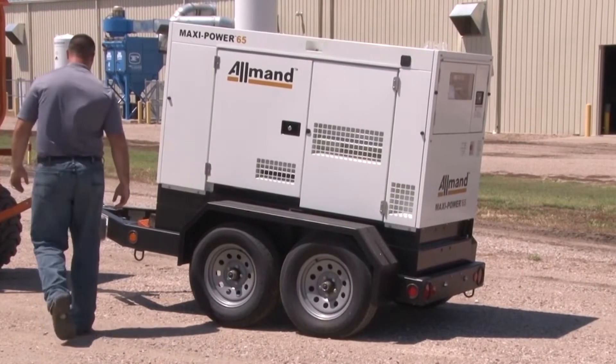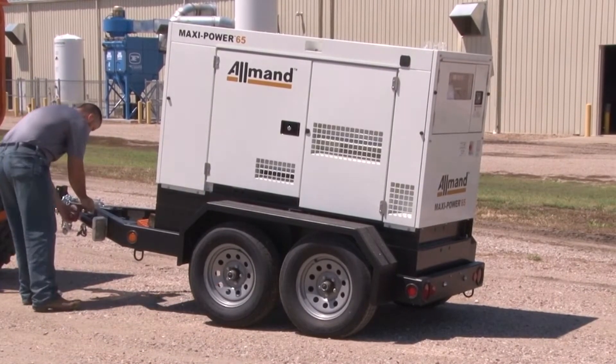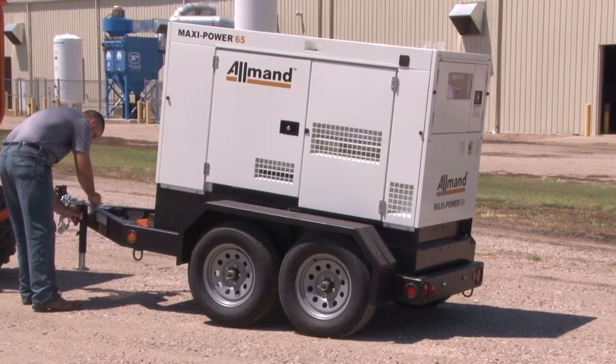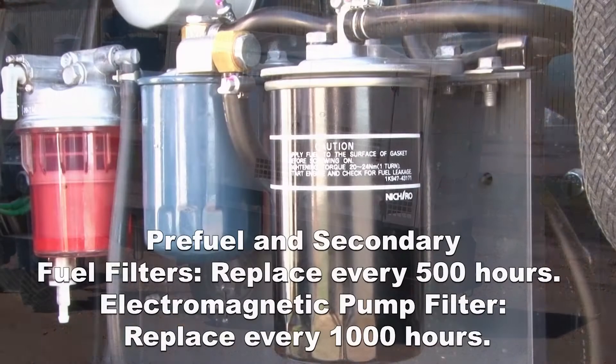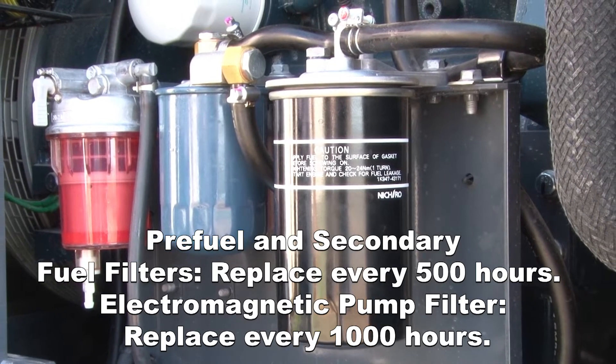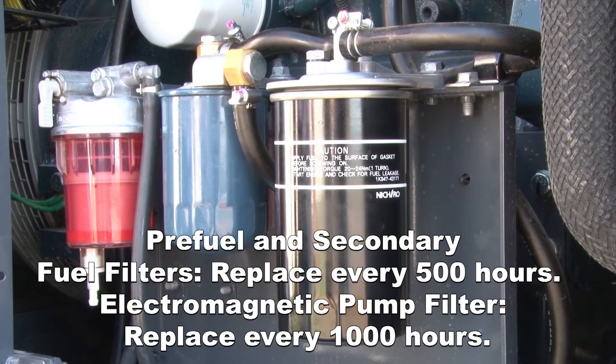Accessible and reliable power is essential to the work that you do. With proper maintenance, Allmand Maxi-Power mobile generators will be ready for you when you need them most. The pre-fuel filter and secondary fuel filter should be replaced after every 500 hours of use, with the filter inside of the electromagnetic pump being changed every 1,000 hours.